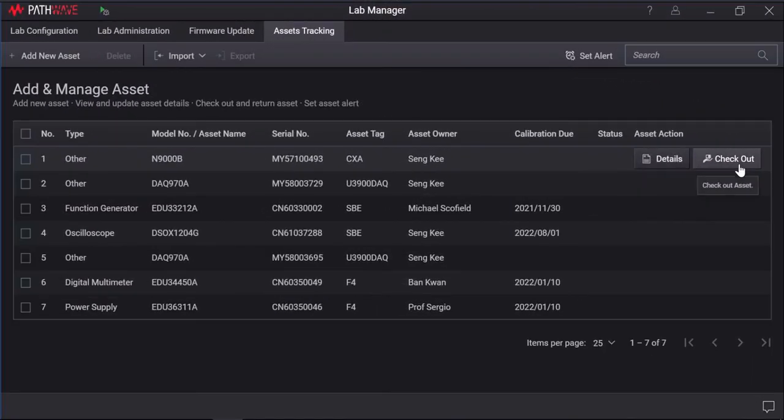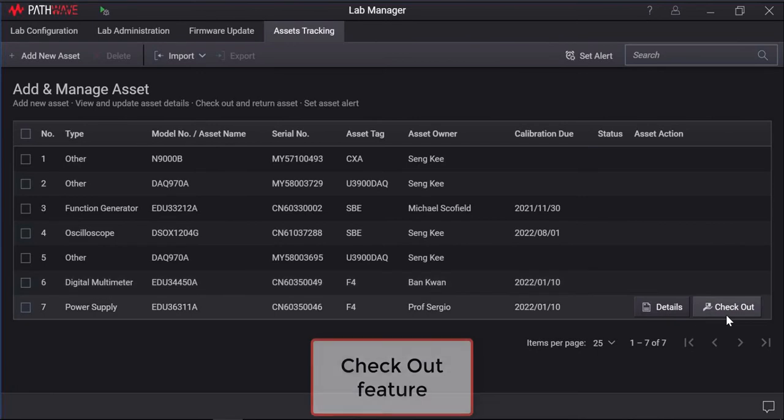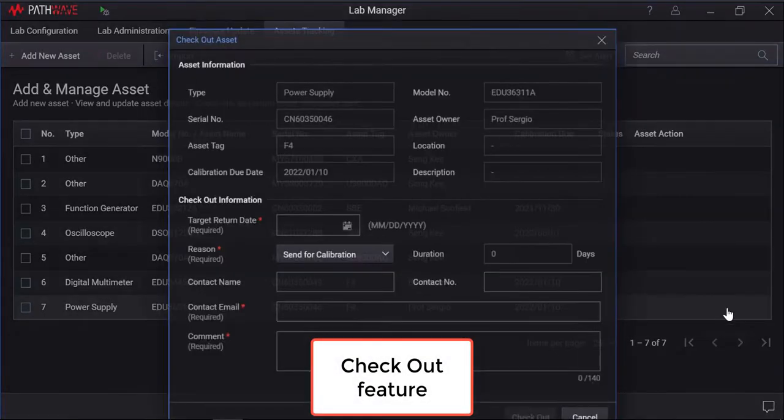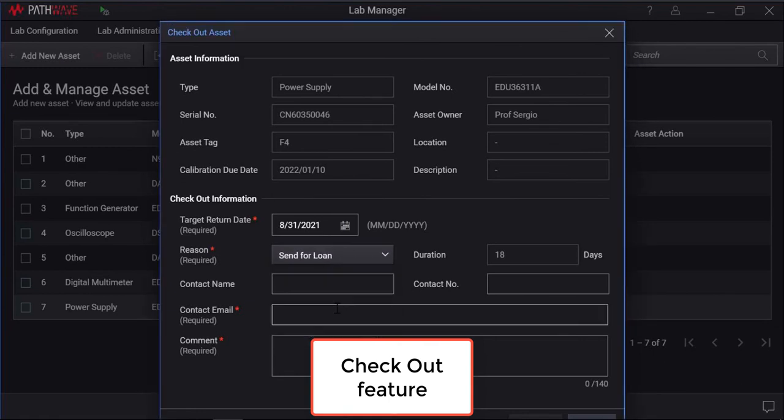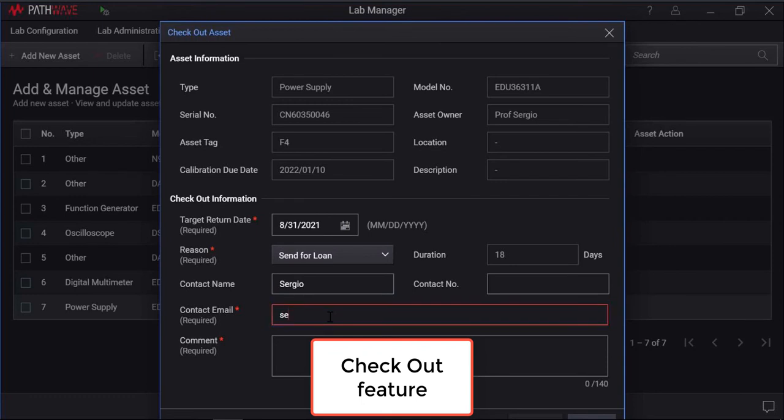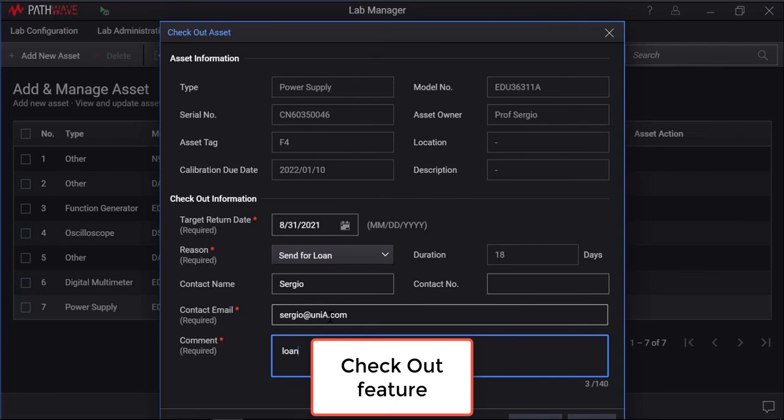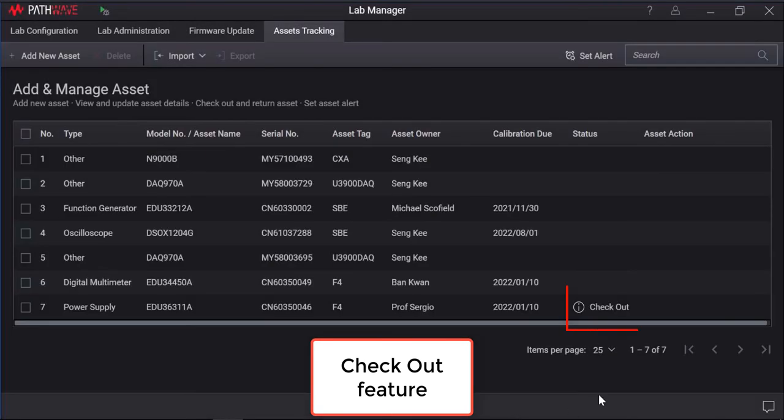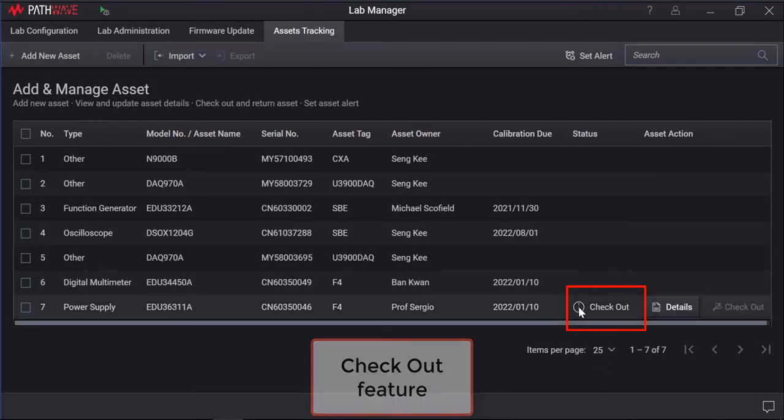The asset tracking checking out feature is useful for tracking the physical locations of the instruments where it is often sent out for loan or calibration. To check out an item, select the desired item for checking out. Fill in the checkout information. Click checkout to check out the item. The item will now be stated as checkout under the status column.